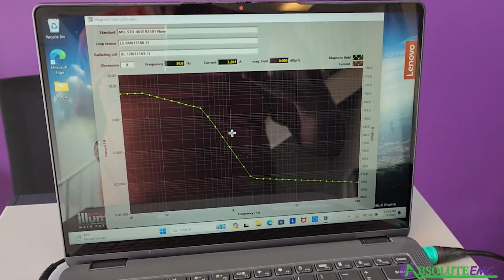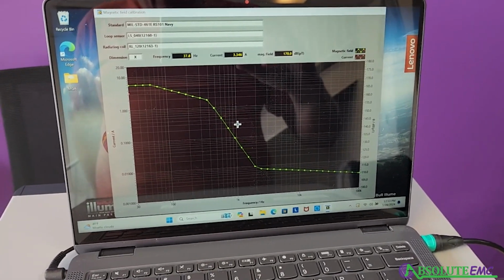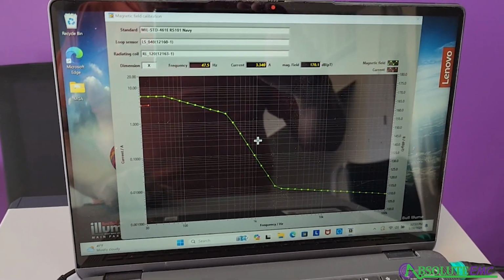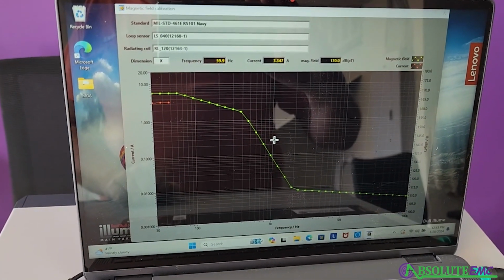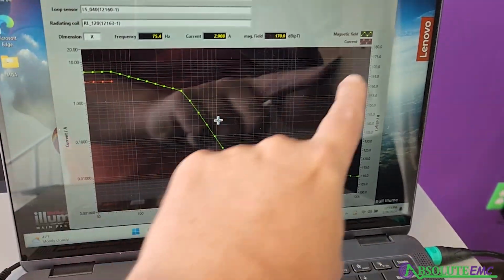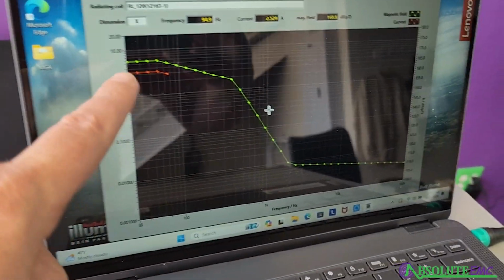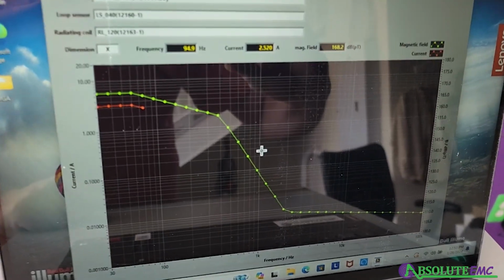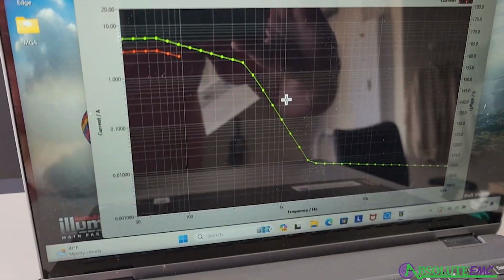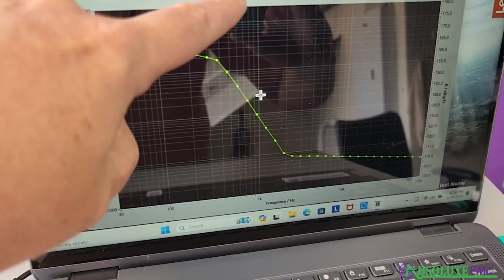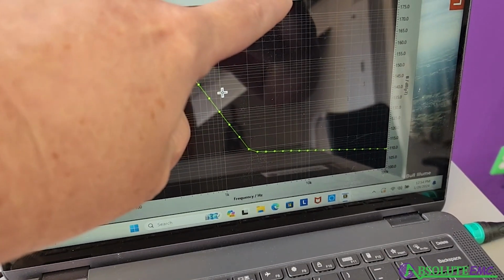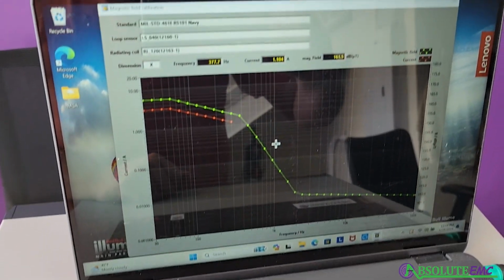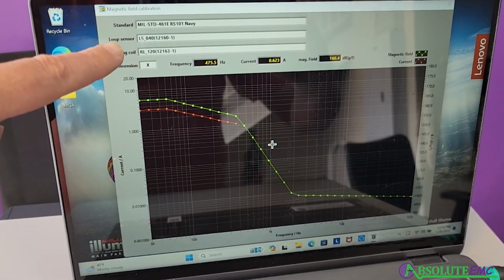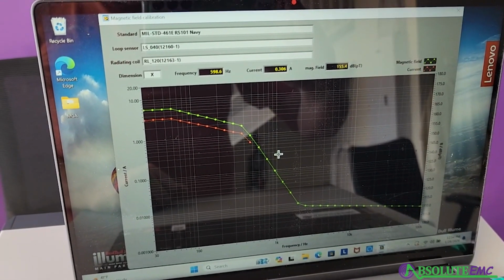Okay, so we're running our field calibration with our loop sensor and our transmit loop. The green line is showing the target level of the field, and that's on this axis over here, and the red line is showing our current level that we're measuring, and that's on this axis here. Additionally, we have what frequency we're at, the current that's actually measured, the mag field that we're shooting for, the key for the different colors, and then of course you have the frequency on the bottom. And all the information is there, with what standard, what loop sensor, and what drive coil or gain coil we're using.